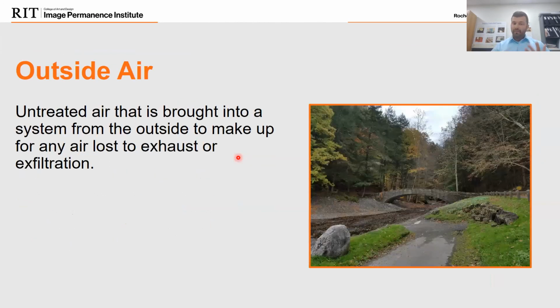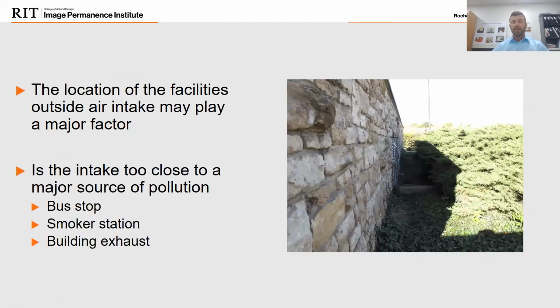And our outside air, that is exactly what it is. It's untreated outside air that's brought into a collection space to make up for any lost air, exhaust air, or exfiltrated air. So we have that outside air. One key component in this is the location of the outside air intake at your facility, and it could play a major factor in this.